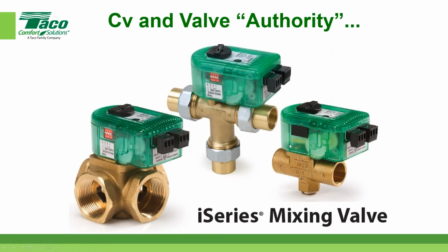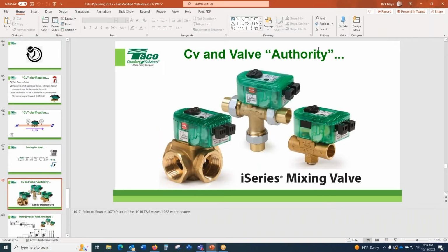So, any questions? Why is the CV value on your 3/4 inch Century greater than the 1 inch? That's a great question. The actual ball size is the same within the 1 inch as it is the 3/4. And the Venturi effect of the reduction in going from 1 inch to 3/4 inch creates a little more turbulence. Imagine a Venturi in your mind. It's creating a little bit more turbulence and therefore a little bit higher pressure drop.